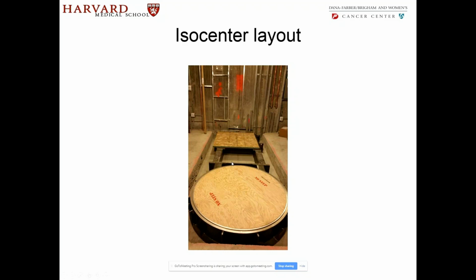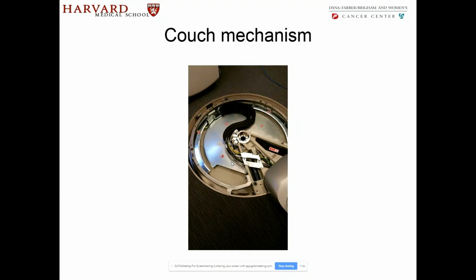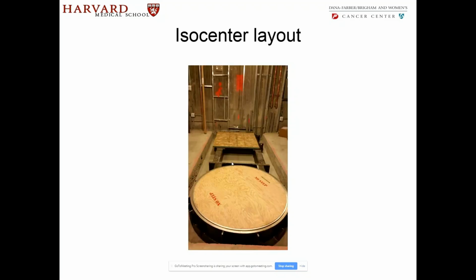the ISO center was laid out. Now, here's the interesting part. Before the Linac is placed, the couch ISO center and the Linac ISO center are put in position. This is the couch mechanism. So before the Linac is placed, the couch has to be placed. The couch, once it is placed, cannot be moved. So that's one of the tricky parts with the Linac. Now, the Linac is actually heavier than the couch, but the couch is the one that moves around the ISO center, and its ISO center is fixed once it is put in place.